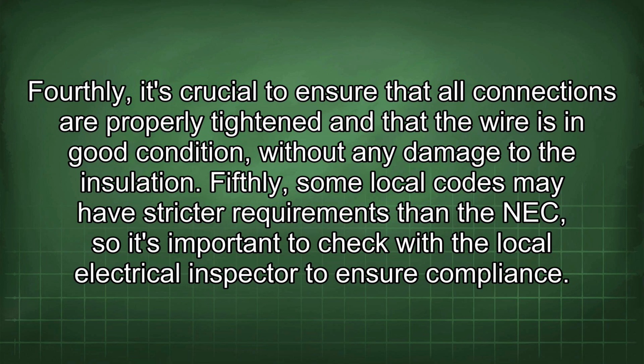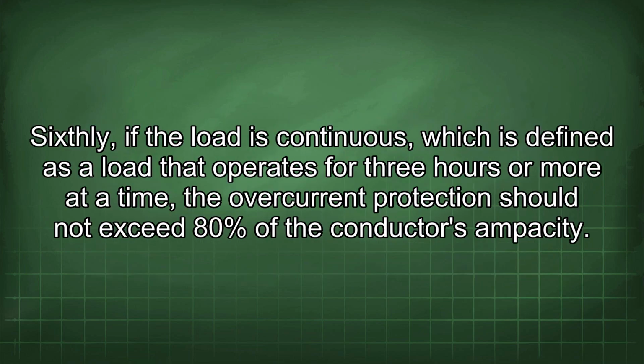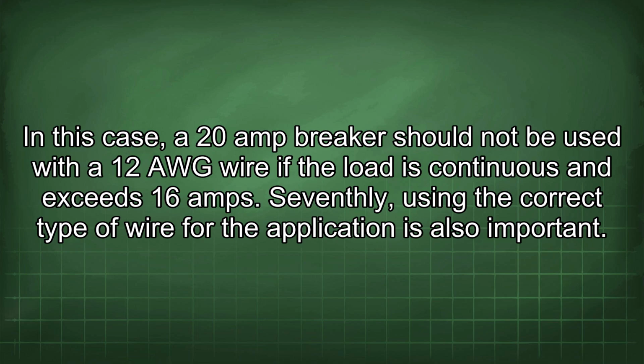Fifthly, some local codes may have stricter requirements than the NEC, so it's important to check with the local electrical inspector to ensure compliance. Sixthly, if the load is continuous, which is defined as a load that operates for 3 hours or more at a time, the overcurrent protection should not exceed 80% of the conductor's ampacity. In this case, a 20 amp breaker should not be used with a 12 AWG wire if the load is continuous and exceeds 16 amps.